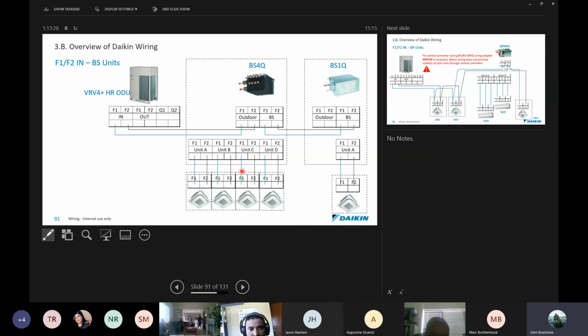Where we have a heat recovery system. Okay, the same story over here, except this time we don't go to the indoor units. We're going to connect up onto the BS boxes. Okay, we have multi-BS boxes and we have single port BS boxes. And on the multi-BS box, you will notice that there are 2 connections, outdoor and BS. And this is where the guys tend to get it a bit wrong, but it's just something to try and remember. Okay, you go from the F1, F2 indoor. Okay, so the outdoor unit is sending the cable to the indoors, but the BS box is looking back at the cable coming from the outdoor.